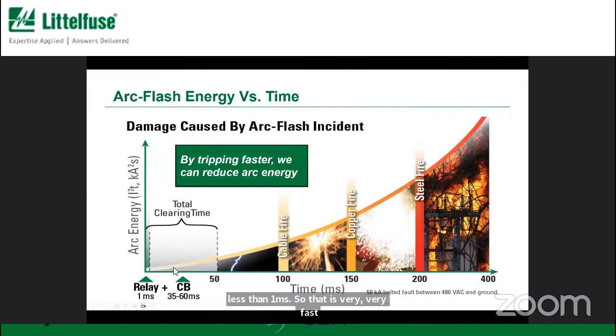Now, the breaker has an operating time to clear, but at least on the relaying side, we are giving that signal as fast as possible. And by opening the circuit and clearing in that type of 50, 60 millisecond time frame, compared to 100 or 200 or longer milliseconds, in many cases the arc energy is reduced by 50, 80, 85%. So a huge reduction in the amount of energy.